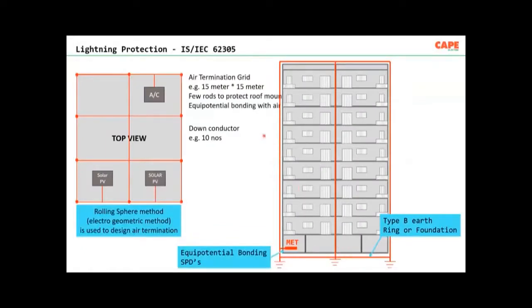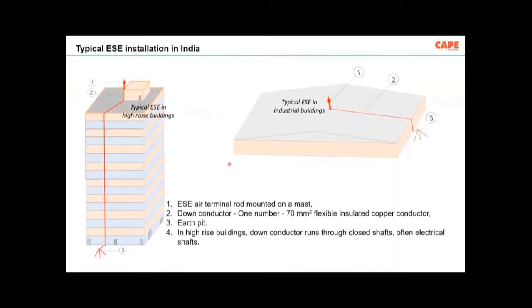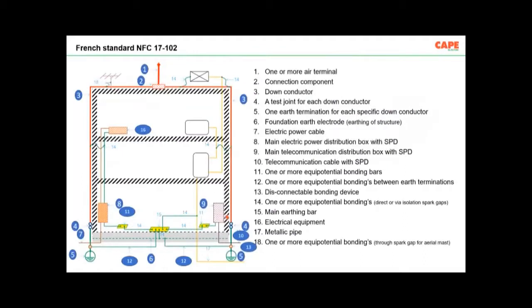This is the explanation from a global, very well accepted standard, 62305. But whenever it comes to earthing, what do we have? We have a rod at the top of the building. I'm not saying all the buildings, but most of the buildings. There is a rod, an early streamer emission rod at the top, one down conductor and one earthing. Unfortunately, this kind of connection is not recommended in the ESE standard itself. There is an ESE standard which is called NFC. So the standard of the French code is explaining in this fashion.